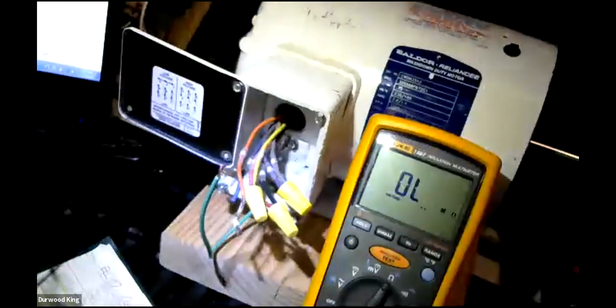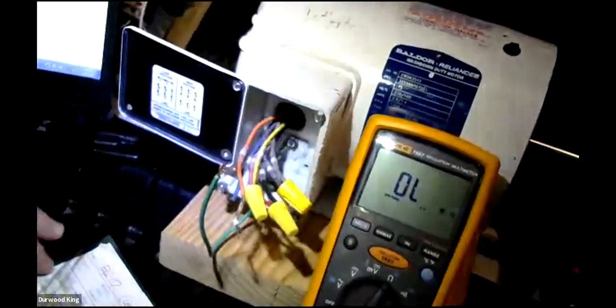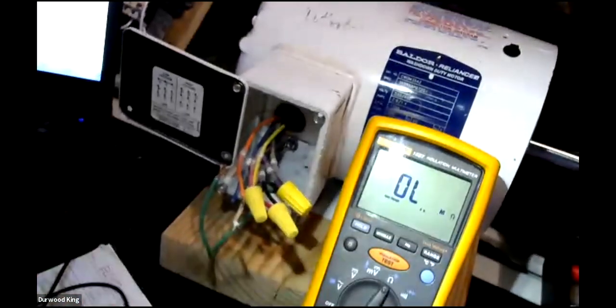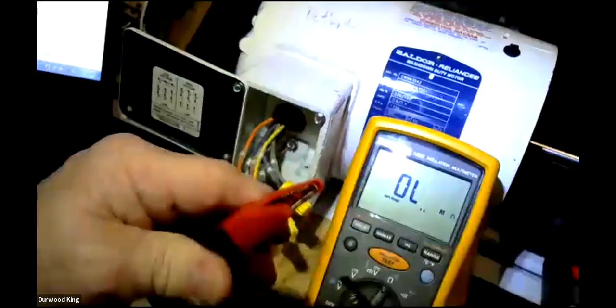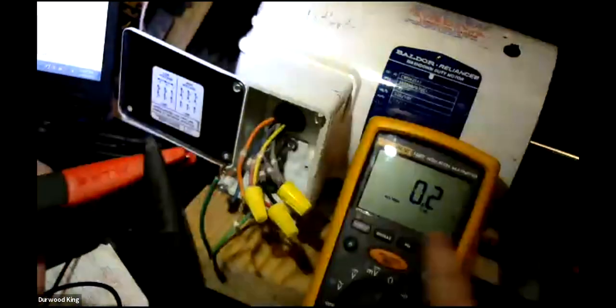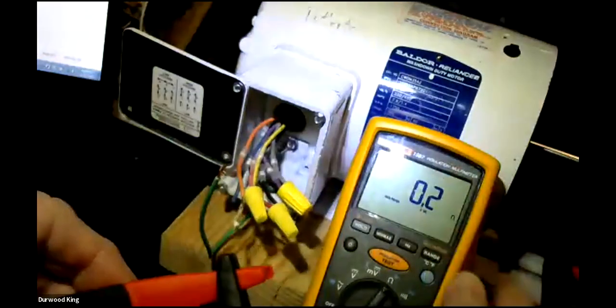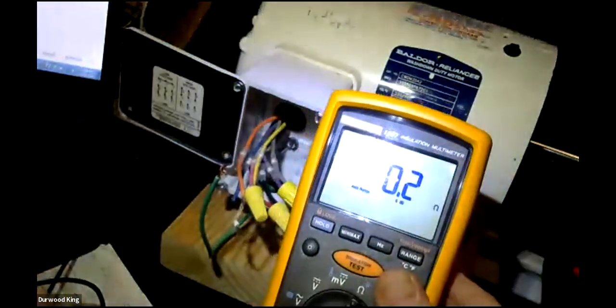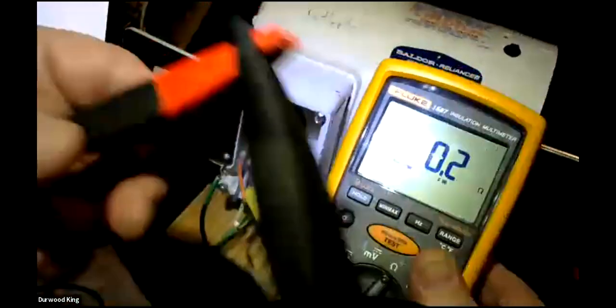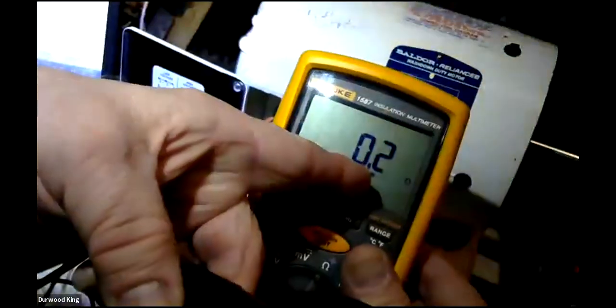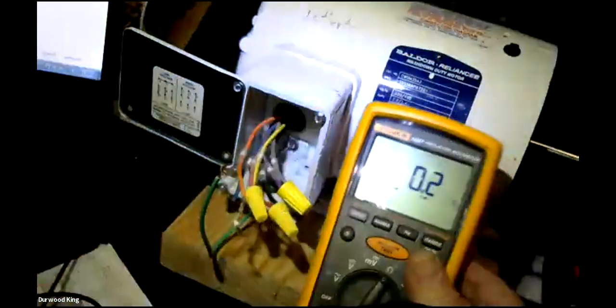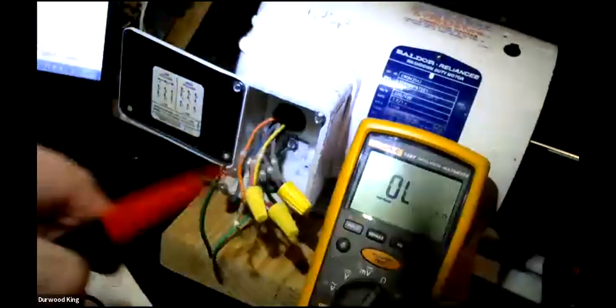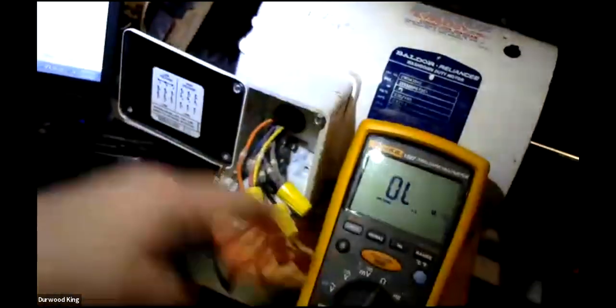So anyhow, now let's take the leads and see where they're at. You can also check here. You put these together and make sure it reads less than 1. That's 0.2 ohms. You see that? So you want to make sure that your test leads are good before you do any of this. You're going to make sure the meter's right and that the test resistance of the leads is very, very low like this. Not K ohms, but actually ohms. Okay, now we know that's fine. So the meter and the leads are good. Don't let a bad meter make you think you got a bad motor and change the motor for no reason.